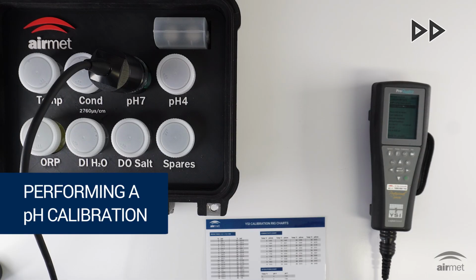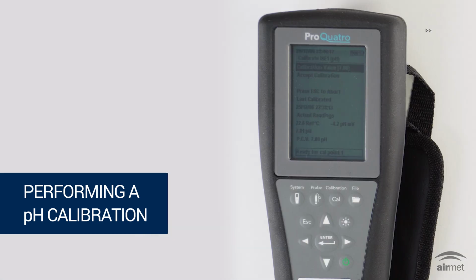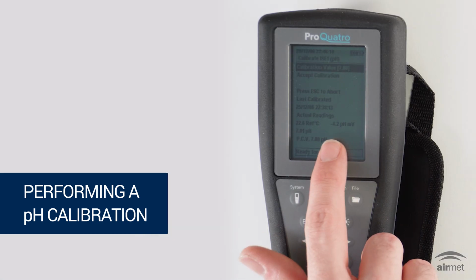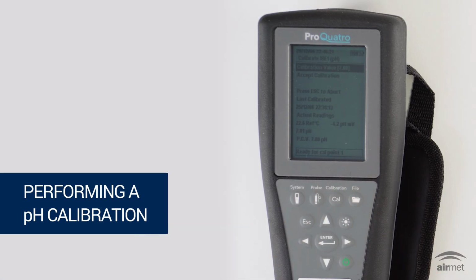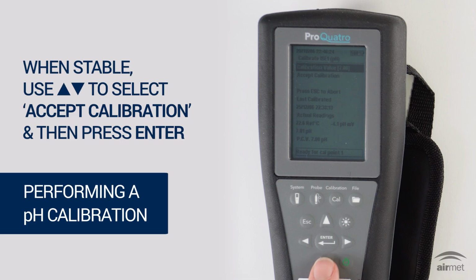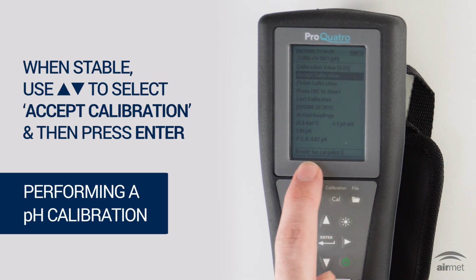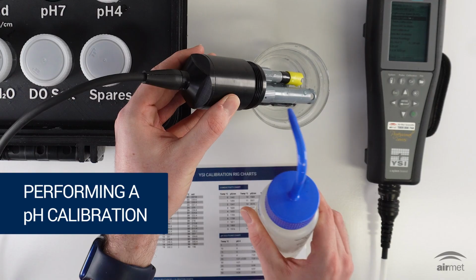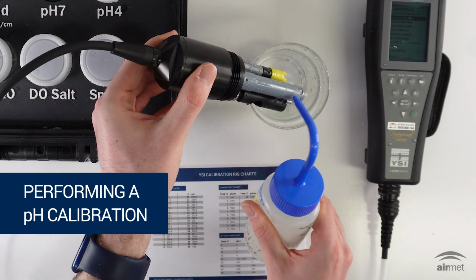Allow the readings to stabilize for approximately 40 seconds. The instrument displays the actual readings and adjusts automatically for the buffer temperature. When stable, highlight Accept Calibration. The instrument confirms success and prompts for the next buffer. Rinse the probe between buffer solutions.